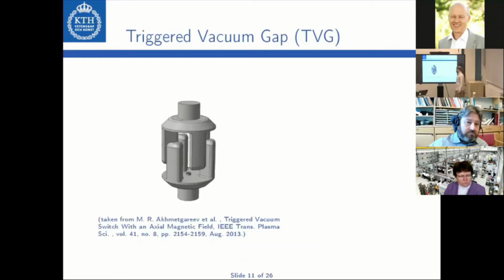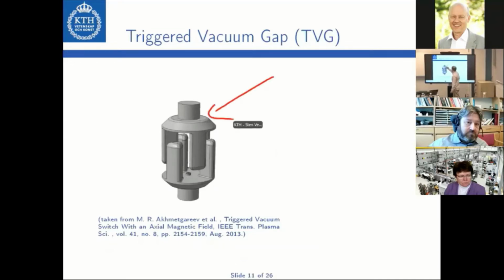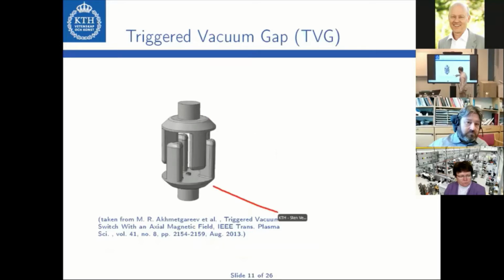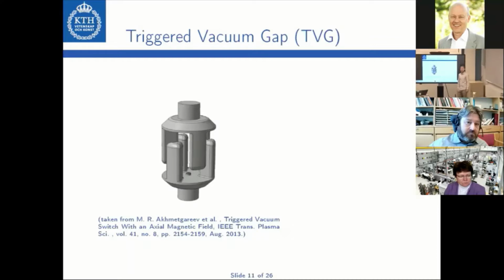The triggered vacuum gap consists of two main electrodes. This is the anode, and this is the cathode. The triggered vacuum gap also has a third electrode, which is the triggering electrode. In order to turn on the triggered vacuum gap, a high voltage pulse is applied to the triggering electrode, which initiates a breakdown between the triggering electrode and the cathode. And here there's some current flow.